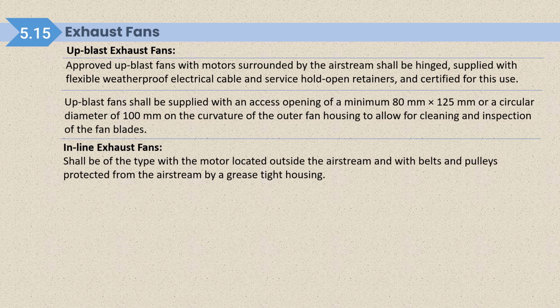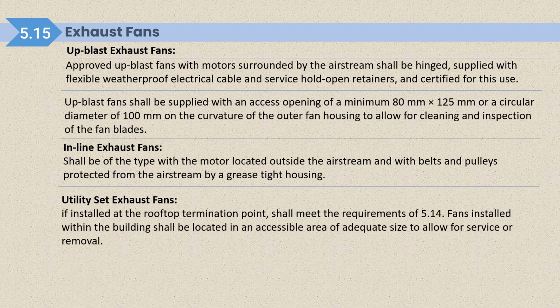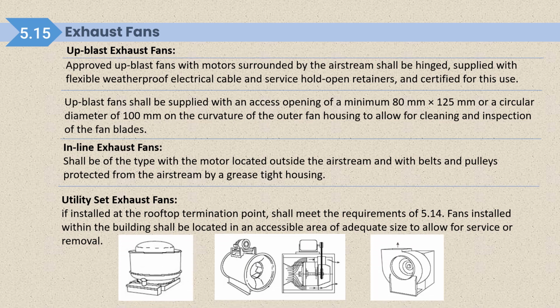Inline exhaust fans shall be of the type with the motor located outside the airstream and with the belts and pulleys protected from the airstream by a grease tight housing. Utility set exhaust fans, if installed at the rooftop termination point, shall meet the requirements we have already discussed in 5.14. Fans installed within the building shall be located in an accessible area of adequate size to allow for service or removal. So these are the fans we were talking about: the first is an upblast exhaust fan, the second is an inline exhaust fan, and the third is a utility set exhaust fan, which we generally use in exhaust systems.